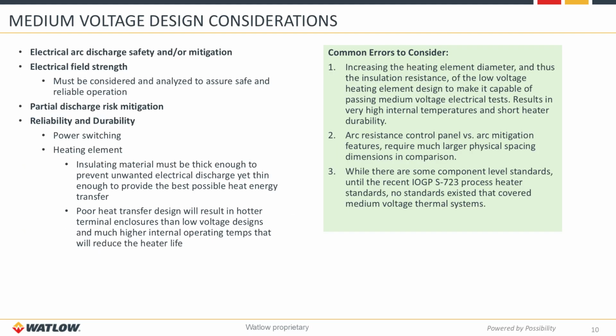I'll next talk about some of the key considerations for designing medium voltage electric heaters. To start, electric arc discharge and safety mitigation is critically important when designing medium voltage heaters, as safety is our priority. Electrical field strength analysis for safe, reliable operation, partial discharge risk mitigation, and reliability and durability, which covers both power switching and heating element design.